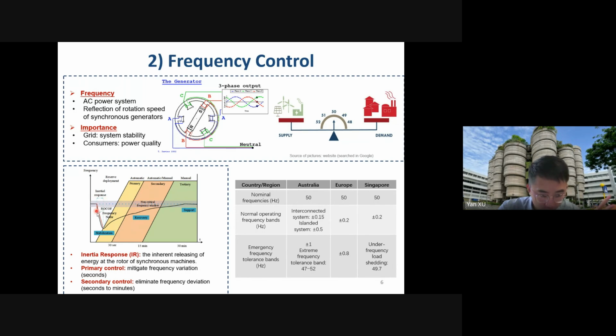Then the frequency will rapidly decrease until a lowest point, which is called the frequency nadir. And this rate of change of the frequency is called RoCoF. Remember yesterday when we introduced PMU, and PMU can measure this RoCoF. And I remember one student asked, how can we calculate this? You can see this RoCoF is easy to calculate. It's just equal to df over dt, right? We just calculate df and divide it by dt.